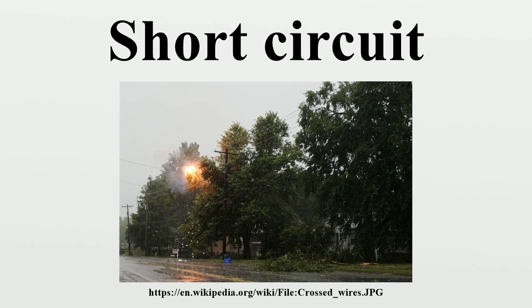Possible effects include unexpected energization of a circuit, presumed to be isolated. To help reduce the negative effects of short circuits, power distribution transformers are deliberately designed to have a certain amount of leakage reactance. The leakage reactance helps limit both the magnitude and rate of rise of the fault current.